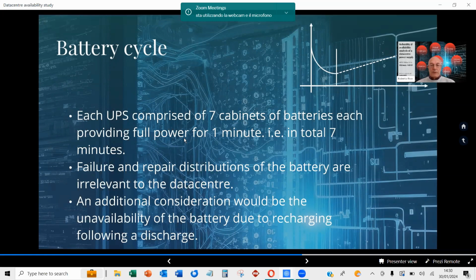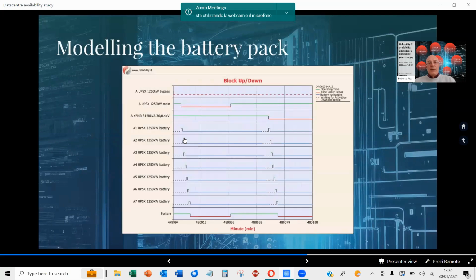So an additional consideration would have been the unavailability of the battery due to recharging after a discharge. Looking at the crude pictorial top right, we had a discharge of the battery, then gradually a recharge, which obviously takes a lot longer than 1 minute. That's the first timing diagram. We did some simulation with separate circuits, putting in a train of battery lasting 1 minute, and a blue line representing the recharge of the battery.